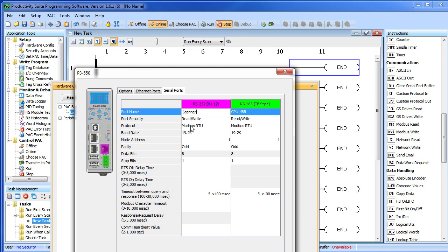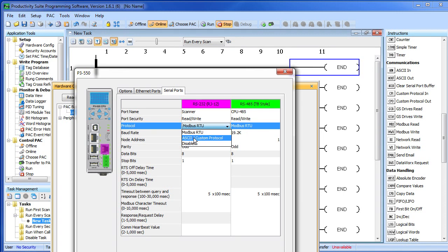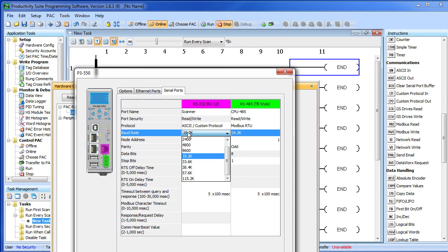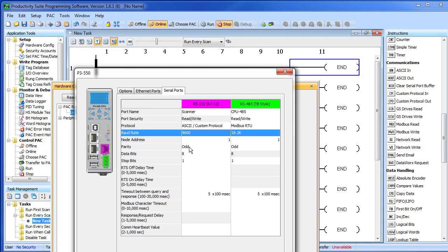The protocol defaults to Modbus RTU. We want to read ASCII, so let's change that to an ASCII protocol. Make sure you don't miss that one. This particular scanner operates at 9600 baud, odd parity, 8 data bits, 1 stop bit—that's correct. Our serial port is set up.